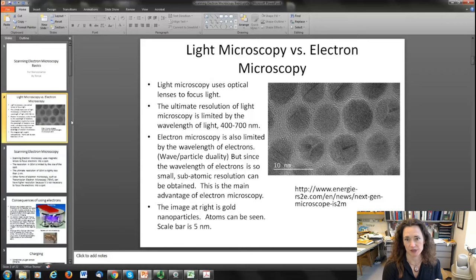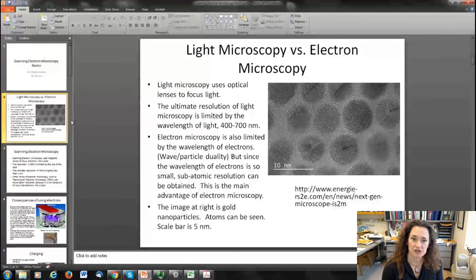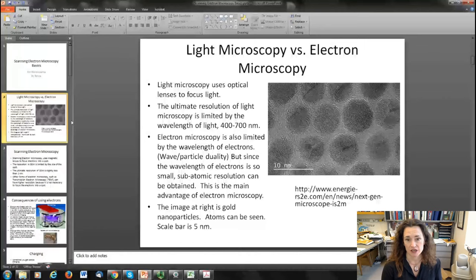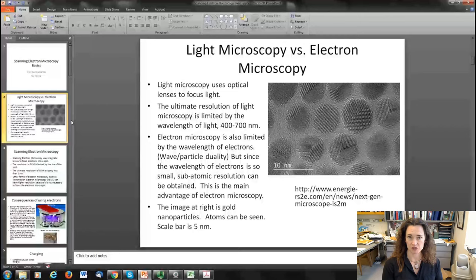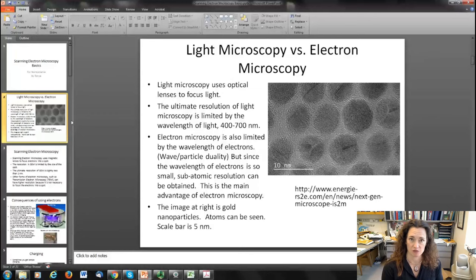Let me talk about some of the differences between light microscopy and electron microscopy. Light microscopy uses optical lenses to focus light down and that is how the image is created. The ultimate resolution of light microscopy is limited by the wavelength of light itself, so you can get some fraction of 400 to 700 nanometers, and depending on what kind of microscope you use you might be able to get a little bit below 400.